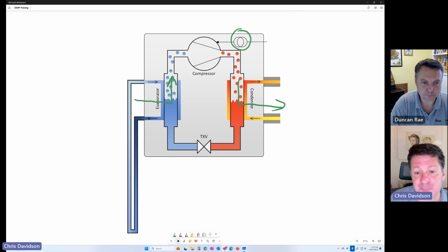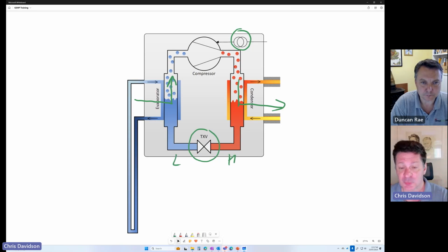And there's also another part down the bottom here, which is the thermal expansion valve. And that's simply a pinhole that keeps the high pressure on one side and the low pressure on the other. It's actually quite complex what goes on inside that TXV, so it's a good one to have a read around if you're interested in a bit more detail. So enough said about heat pumps themselves.